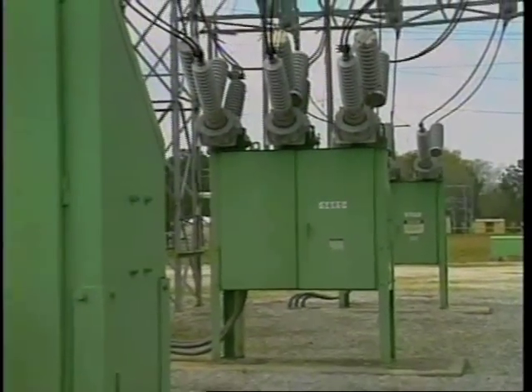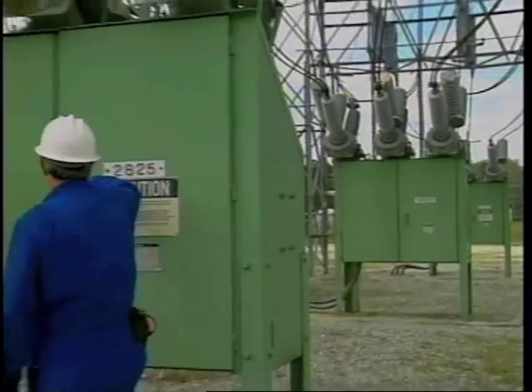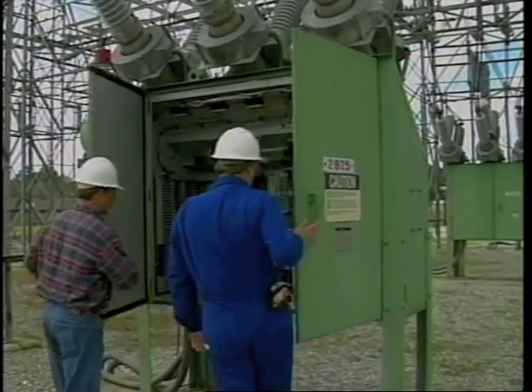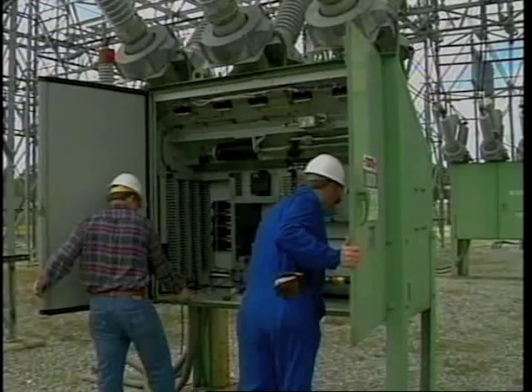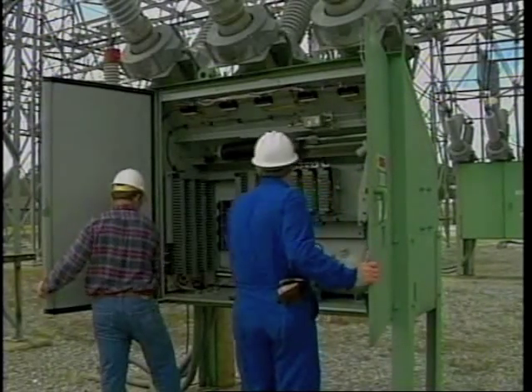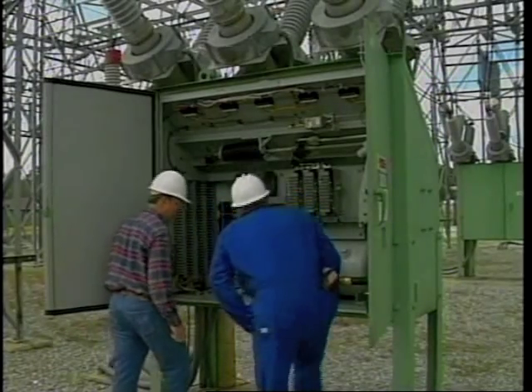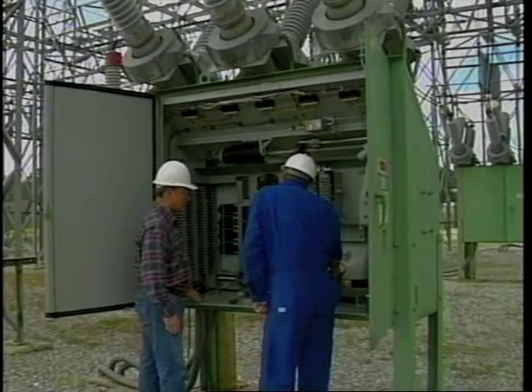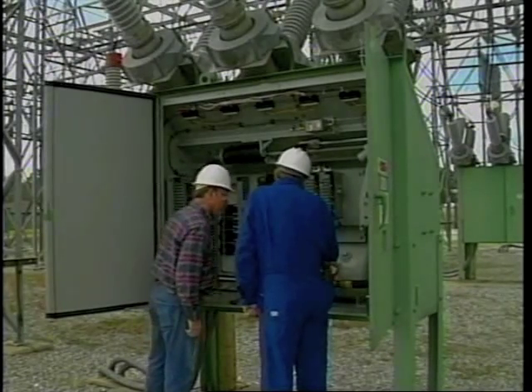Sulfur hexafluoride circuit breakers provide an excellent insulating medium for arc interruption. Sulfur hexafluoride gas has a dielectric strength that is two and a half times greater than that of air. In this program, we'll look at the major components that make up sulfur hexafluoride type circuit breakers, as well as pointing out generally accepted safe work practices for this type of equipment.